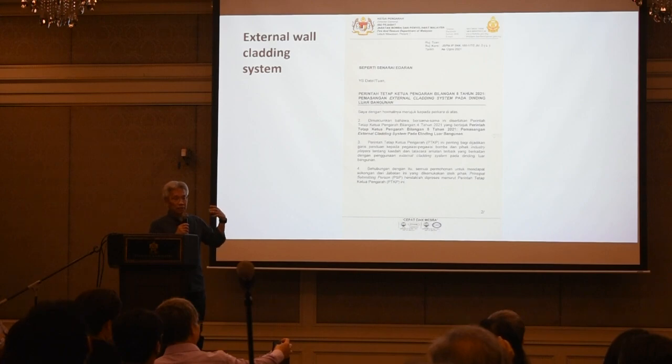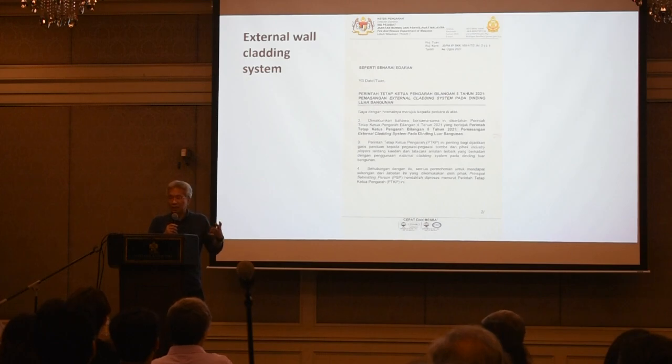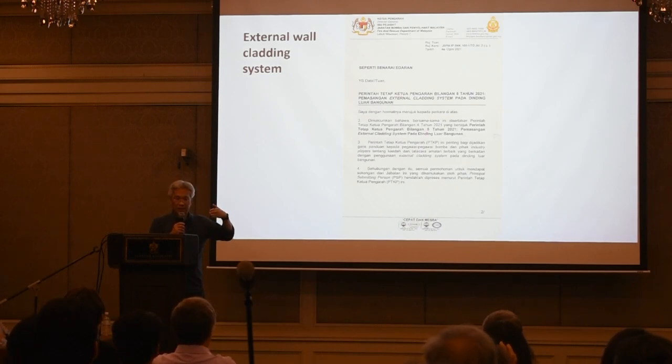So effectively, our UBBL on a passive system already, well, our UBBL is adopted and adapted from the old British ordinances anyway. Right? So the same concept applies. Every single apartment is compartmentalized on the sides, separated from your adjacent neighbor, and on the back or the front separated from all the common areas, the lobbies and the circulation.